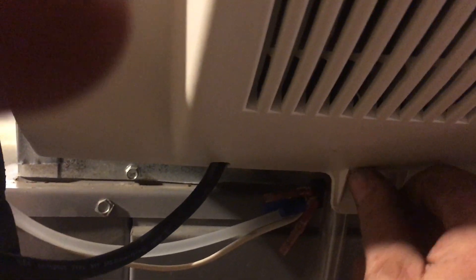It took me about six hours to install this thing and I had to have my tin knocker buddy come over, because this is the only spot on the plenum that was big enough with enough clearance. This duct right here was here, that's why I had him come over — because he can cut a seven-inch hole in there round, and mine would not be round.